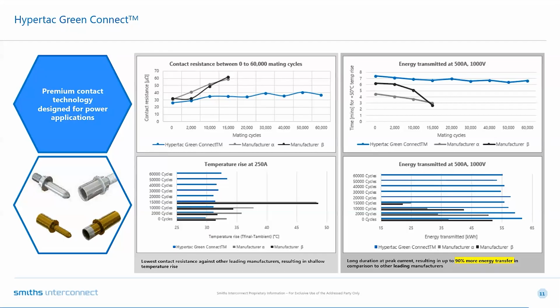Now regarding the peak current, shown on the top right: the same contact rated for 300 amps has 500 amps put through it, and you measure the time it takes for a plus 50 degree C temperature rise. Everything starts well, but you quickly see how the time for manufacturers alpha and beta to reach that rise takes a nosedive.